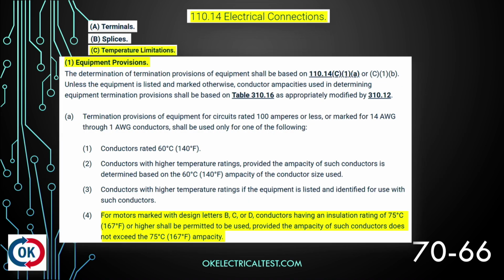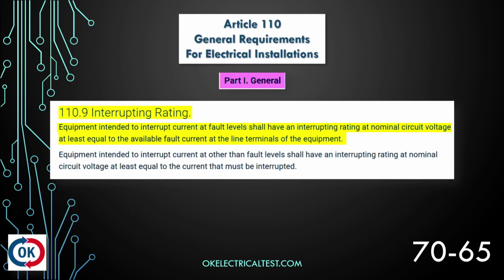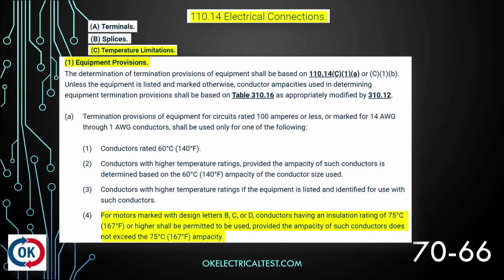Moving on, page 66, we've got 110.14, electrical connections. And so we've got letter A, B, and C. We're going to jump down to letter C, temperature limitations. Now, temperature limitations for what? It's electrical connections. And so what we need to understand is the context of the code as we're going through. As we're reading things, we can see that it's basically organized by these different code references. And these code references are different subtopics of the bigger topic, which is our general requirements for electrical installations. And so here, what they're going to talk specifically about is electrical connections. And specifically what we're going to take a look at is the temperature limitations of electrical connections.